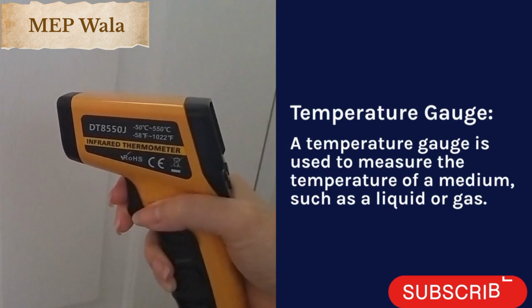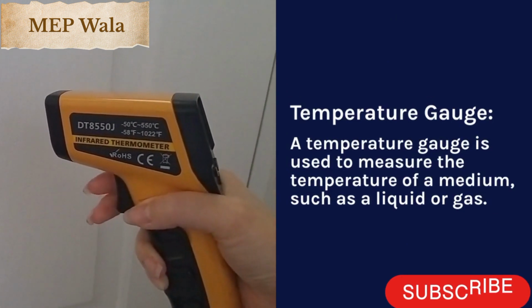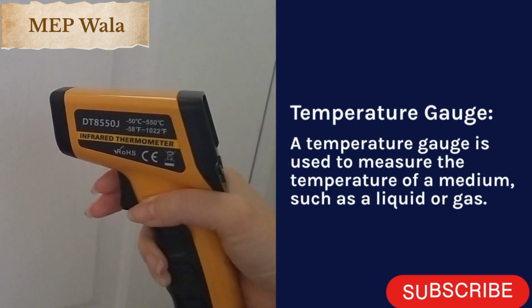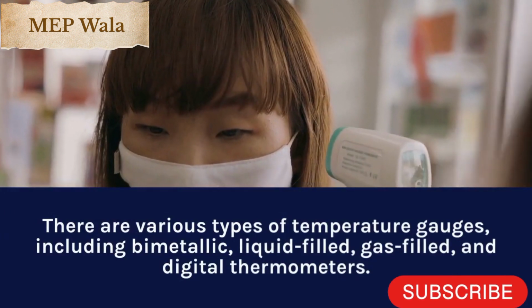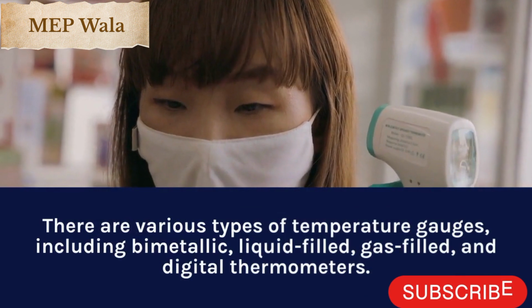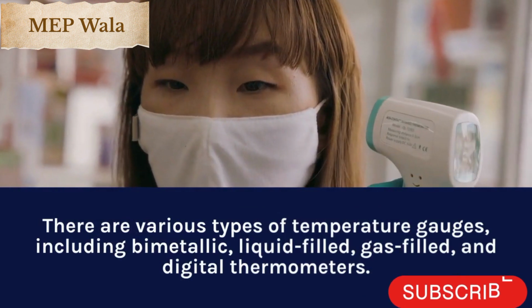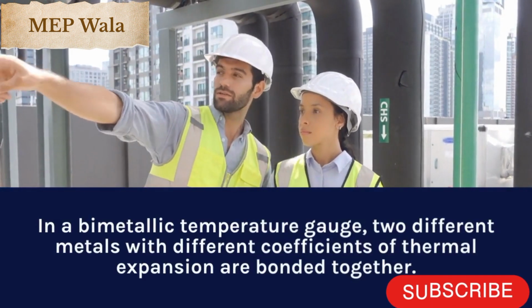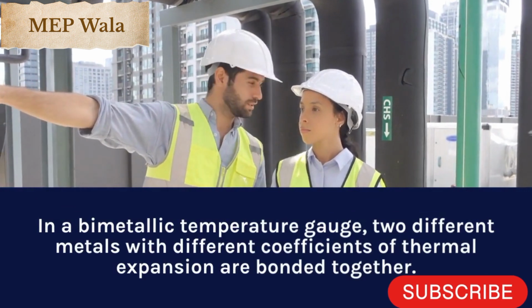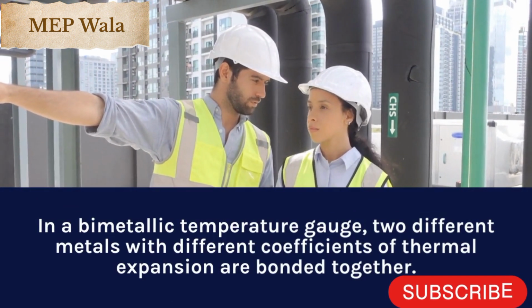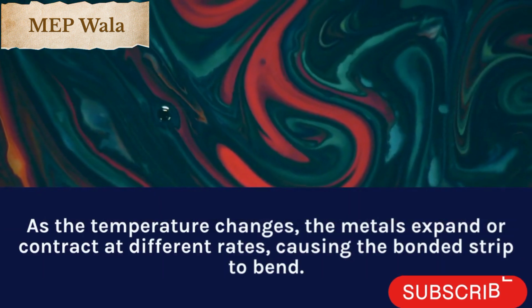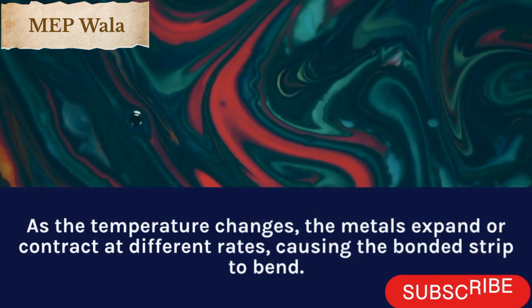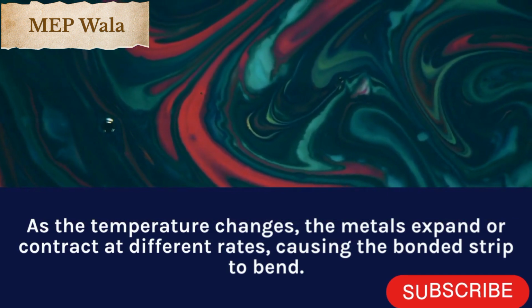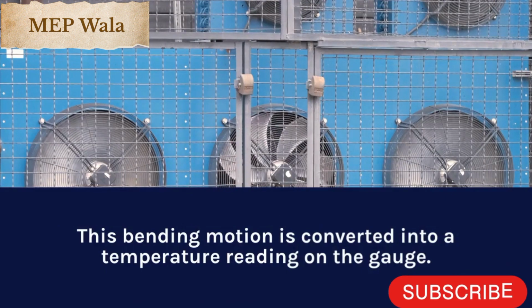Temperature gauge. A temperature gauge is used to measure the temperature of a medium, such as a liquid or gas. There are various types of temperature gauges, including bimetallic, liquid-filled, gas-filled, and digital thermometers. In a bimetallic temperature gauge, two different metals with different coefficients of thermal expansion are bonded together. As the temperature changes, the metals expand or contract at different rates, causing the bonded strip to bend. This bending motion is converted into a temperature reading on the gauge.